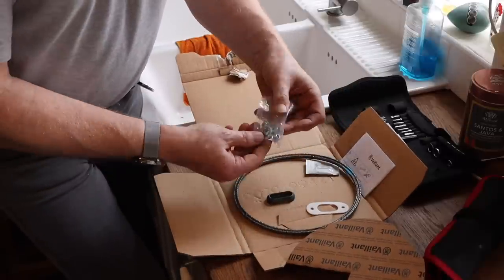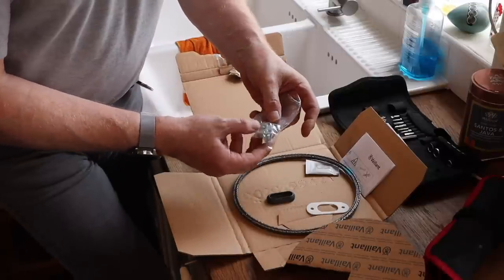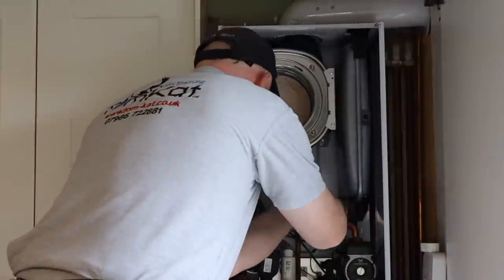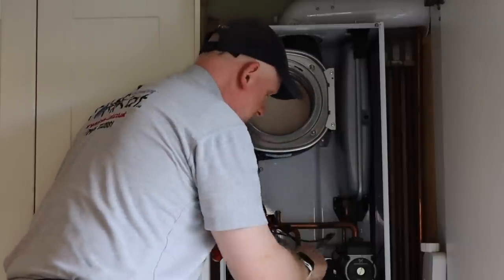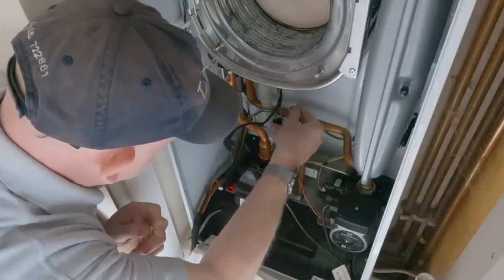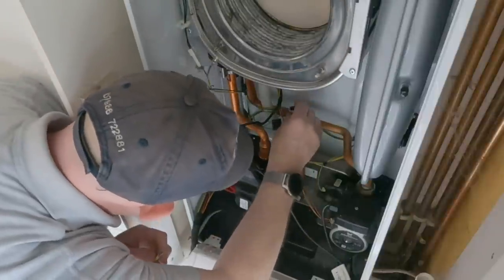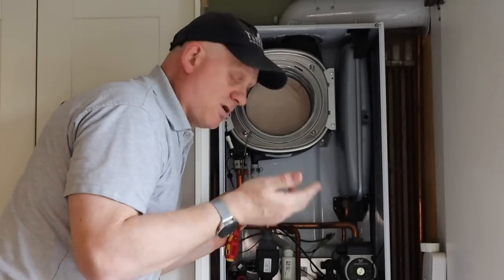First I put the new gas connection on so I don't forget it — that's important. There's a gas connection for the Vaillant and one for the Glow-worm. Using a flat screwdriver, I flick off the old gasket and put the new one on, which is a tight fit. Be careful because it can fall off. Every time you take the heat exchanger off, you need to put a new gasket on.